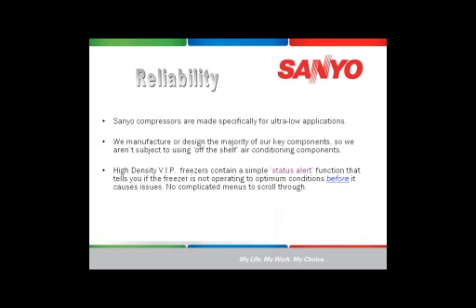On top of that, for reliability, most of our premium freezers have integrated into them what's called a status alert. The status alert monitors the freezer constantly and monitors many things to determine if the freezer is operating at maximum optimum conditions. The purpose of that is to give you a very simple indication that there might be a problem with either your loading, ice buildup, compressor efficiency, or something with your voltage, telling you long before there's a problem that there's something you need to have looked at, to make sure that there is not a problem that's going to haunt you down the road as far as your freezer is concerned.